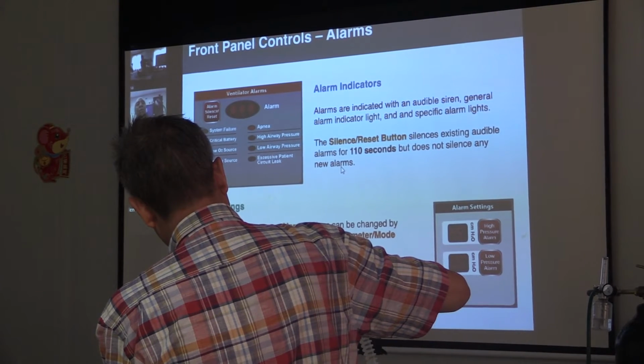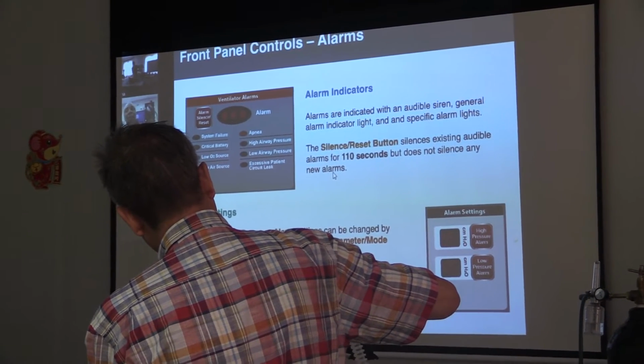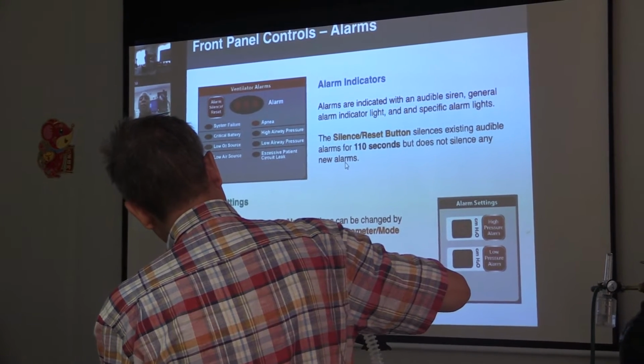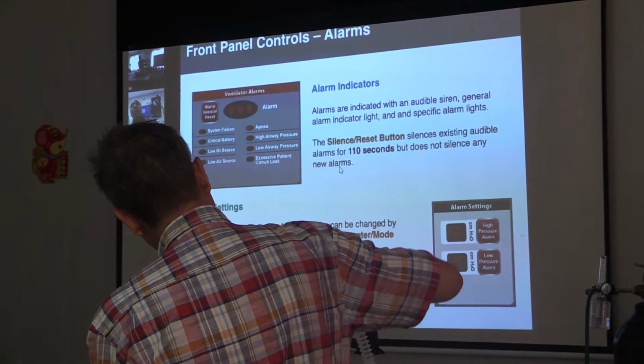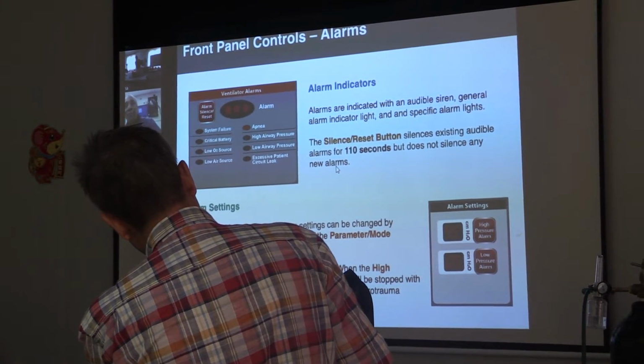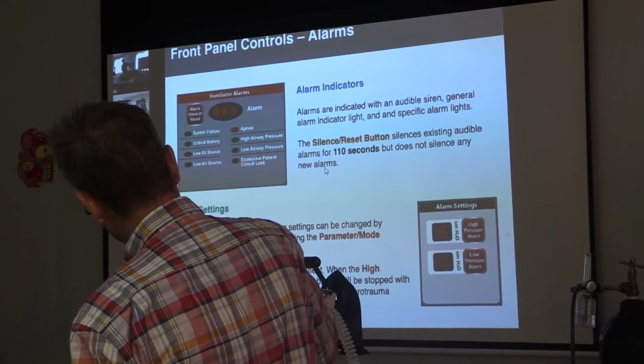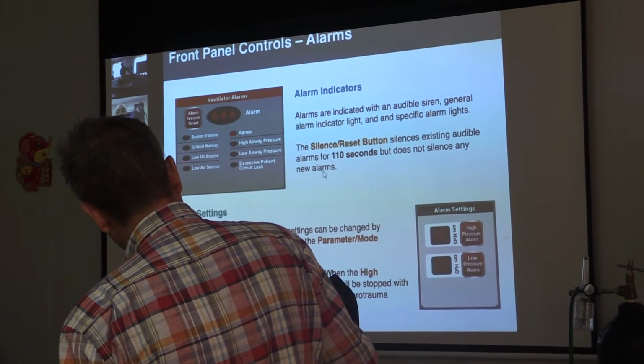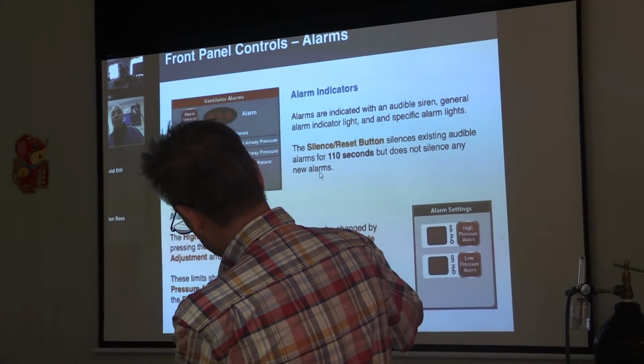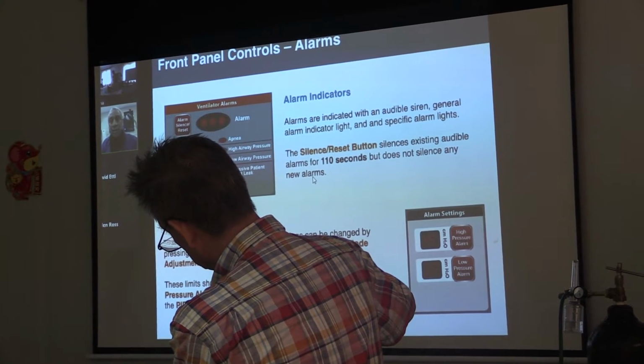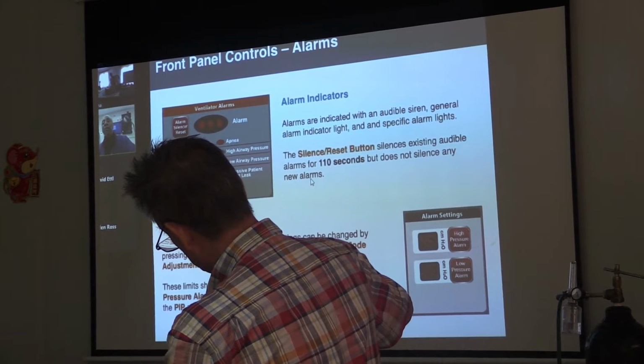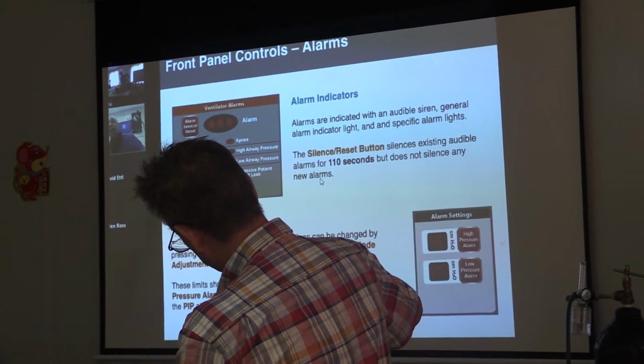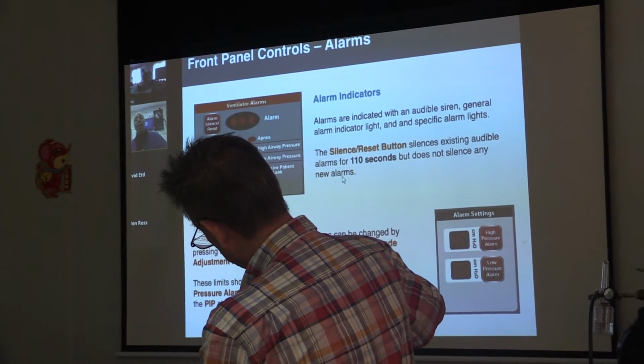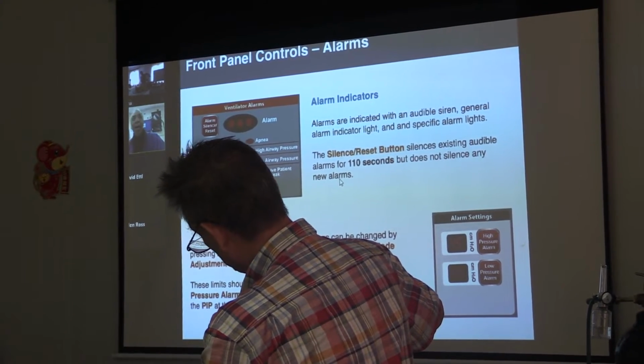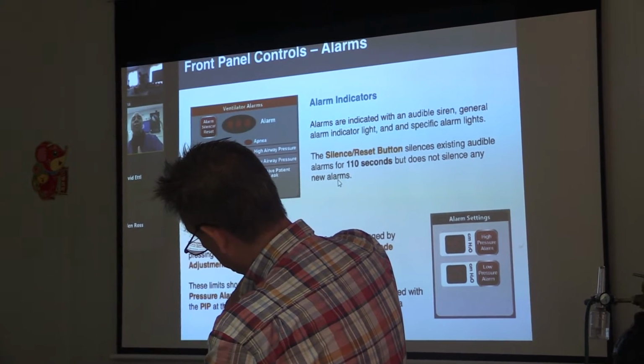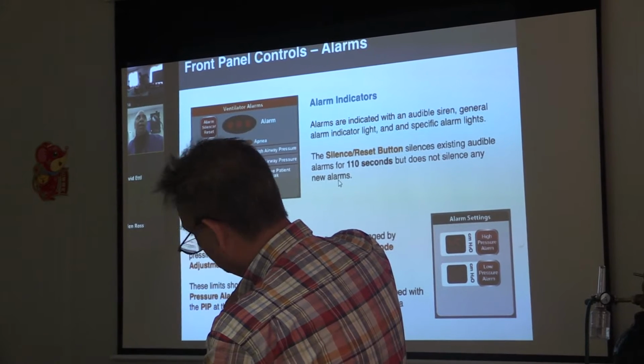So let's say that your high pressure alarm setting is set for 30. But let's say that you need 25 centimeters of water of peak inspiratory pressure to breathe for the patient, and that the patient's PEEP is 10. Well, the peak inspiratory pressure will actually be the 10 plus the 25, which is 35. Since your alarm is set for 30, every time the machine tries to give a breath, it's going to alarm with the high pressure alarm.